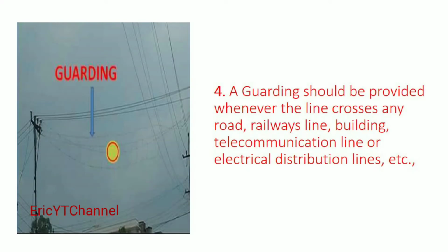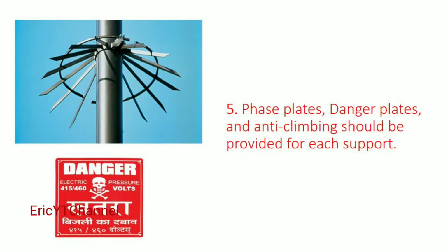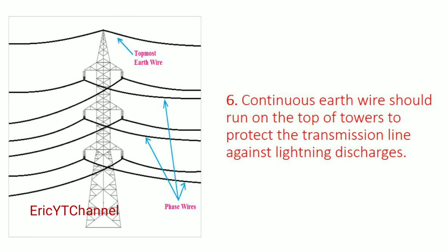Number 4. A guarding should be provided whenever the line crosses any road, railway line, building, telecommunication line, or electrical distribution lines, etc. Number 5. Phase plates, danger plates, and anti-climbing devices should be provided for each support. Number 6. A continuous earth wire should run on the top of towers to protect the transmission line against lightning discharges.